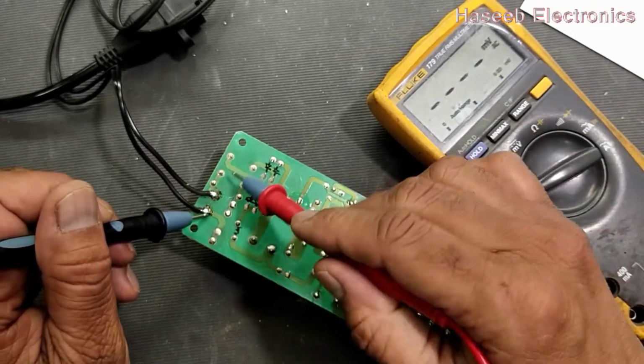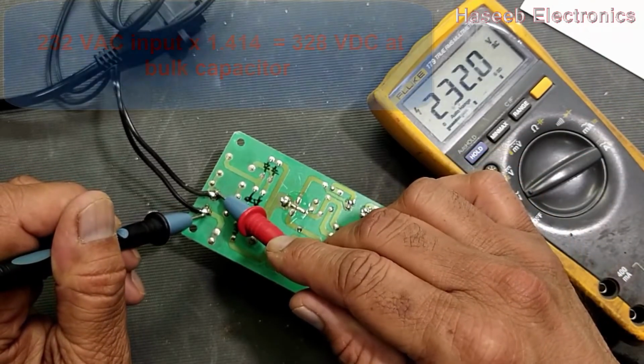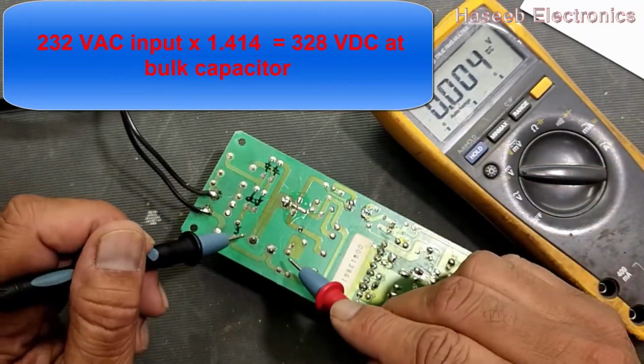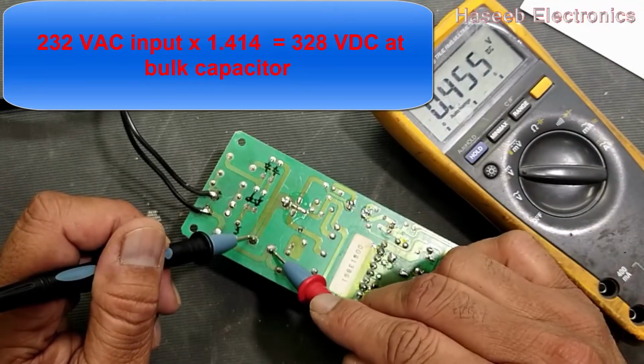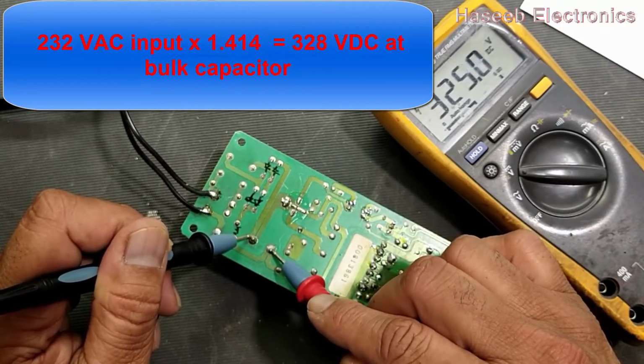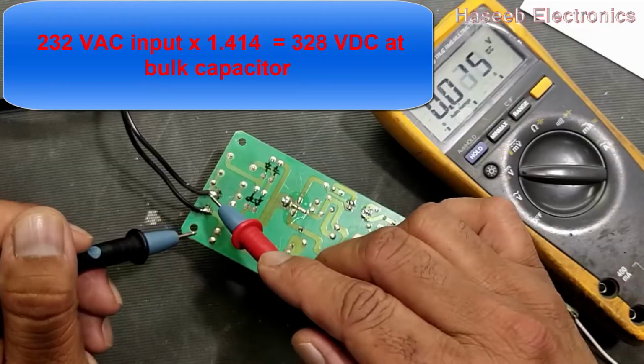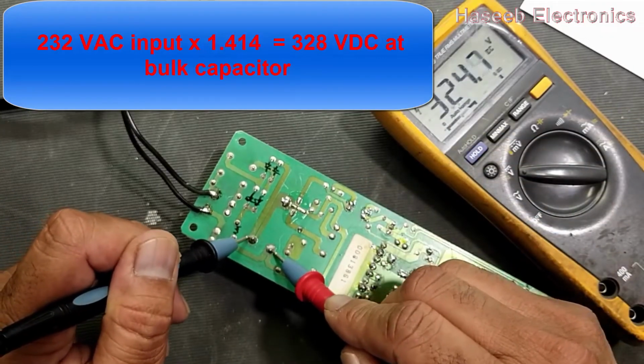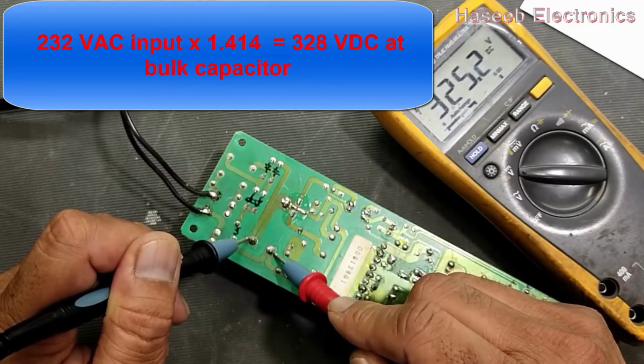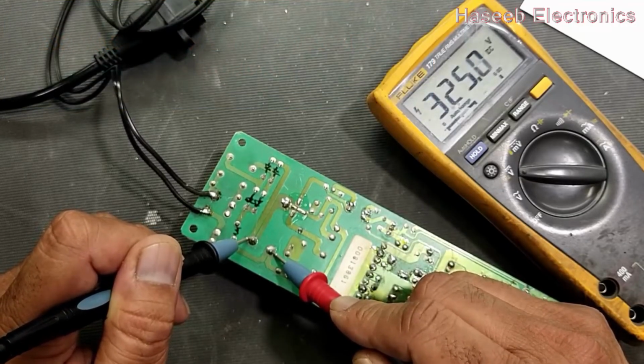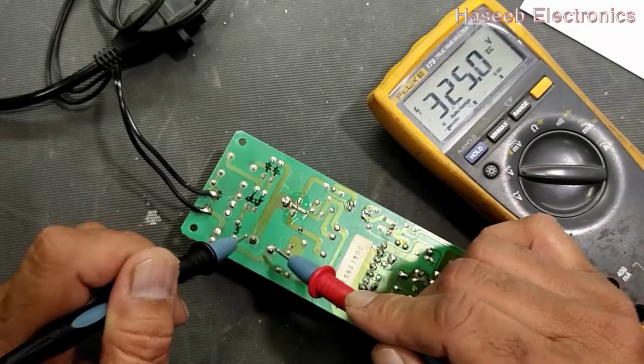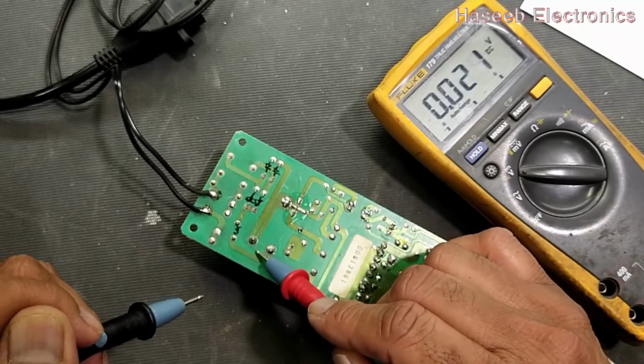Here I applied 232 volts. Multiply it by 1.414 and check the resulting voltage at this point. Multiply by 1.414 and you should get the same voltage here. If it comes to 325 volts as the calculation says, that means this capacitor is good and this circuit is good.